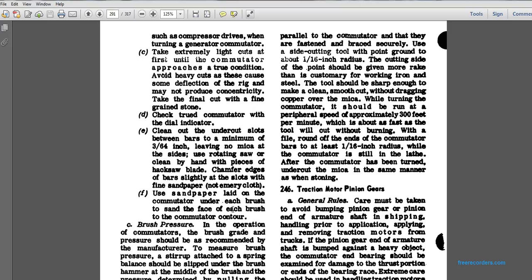Use a side cutting tool, pointed and ground about 1/16 of an inch. The cutting side of the point should be given more rake than is customary for working iron and steel. The tool should be sharp enough to make clean, smooth cuts without dragging copper over the mica. While turning, the commutator should be run at a peripheral speed of approximately 300 feet per minute, which is about as fast as the tool will cut without burning.